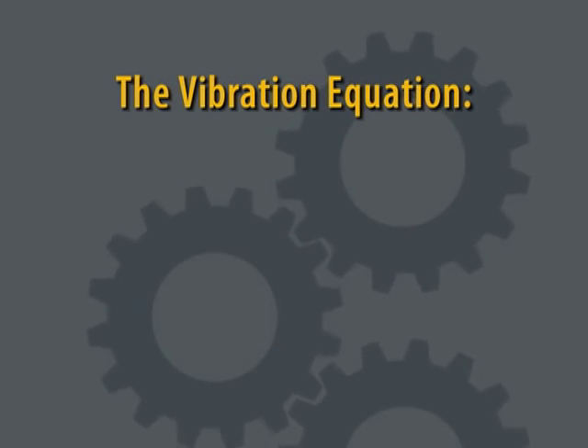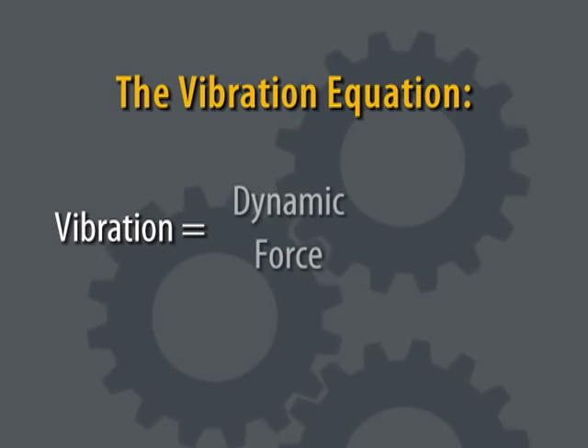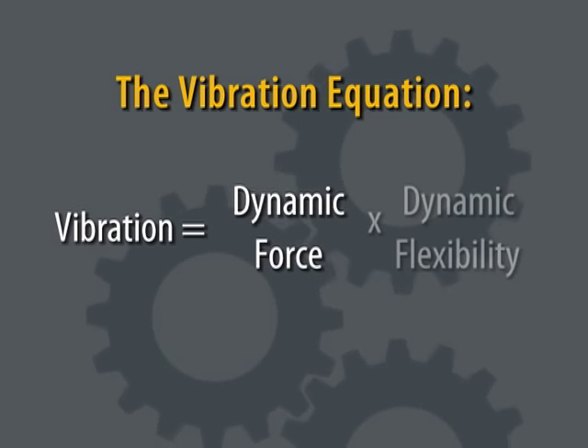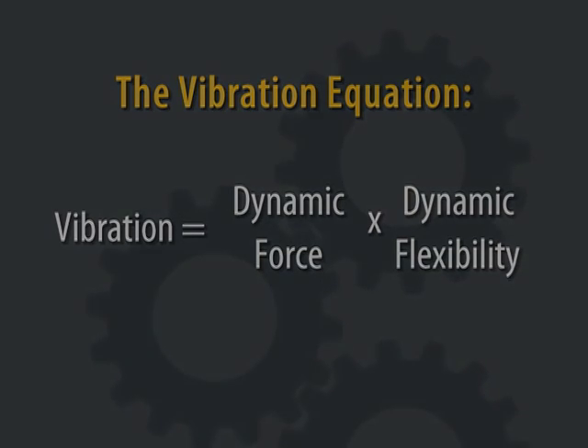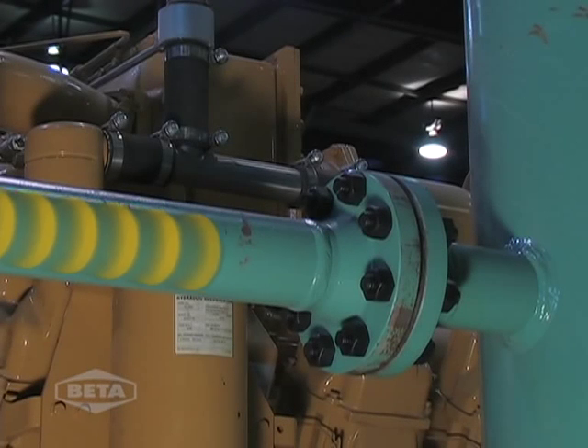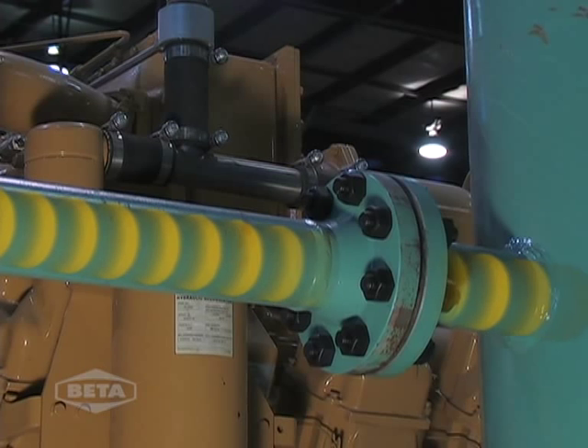These dynamic forces generate vibration as defined in the vibration equation. Vibration equals dynamic forces multiplied by dynamic flexibility. Pulsations are pressure waves created during the reciprocating motion of a compressor piston. Here's a simple example.